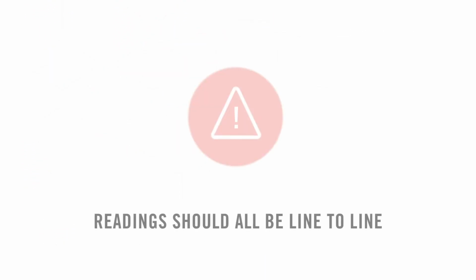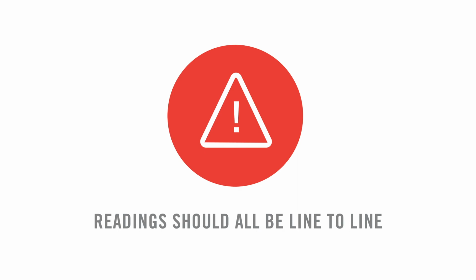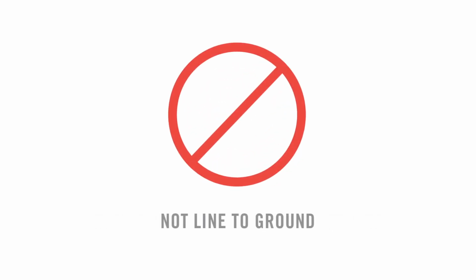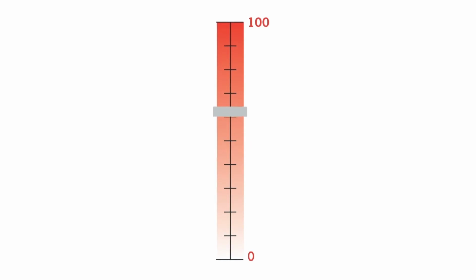Before you begin, please note, when you're taking readings, they should all be line to line, not line to ground. In addition, all readings should be taken with the heaters installed and a control signal of 100%.